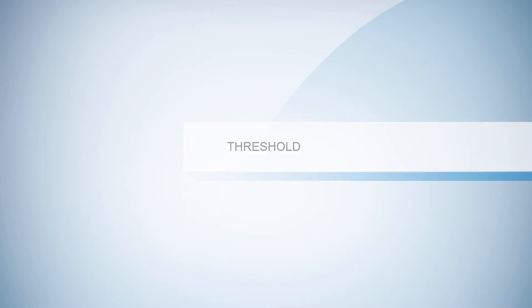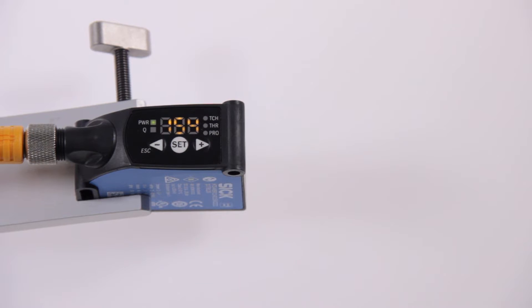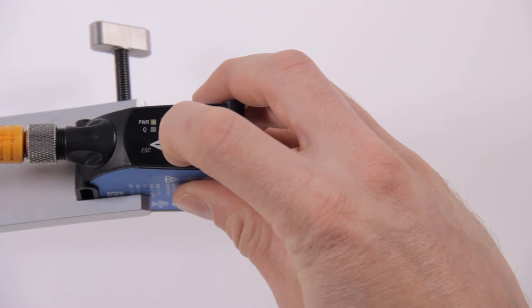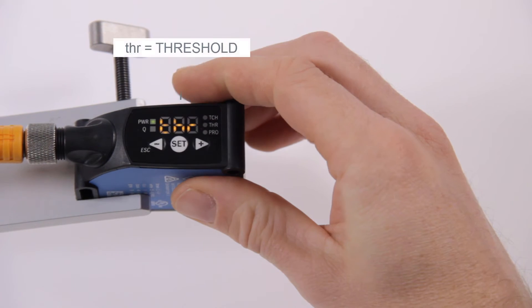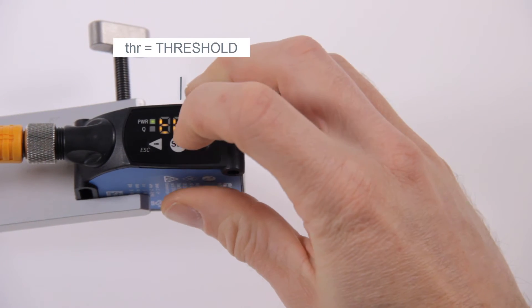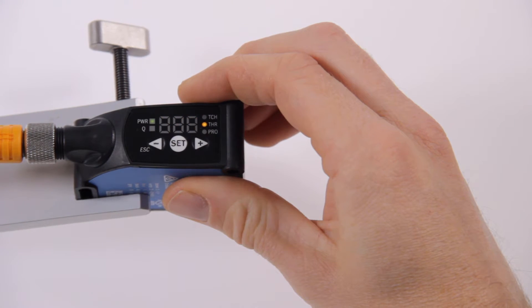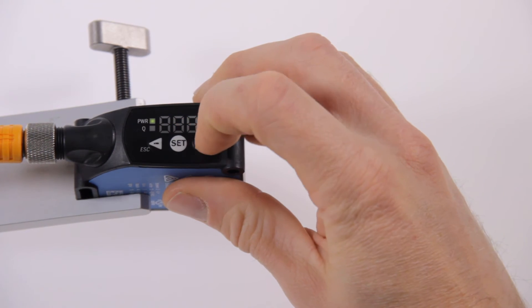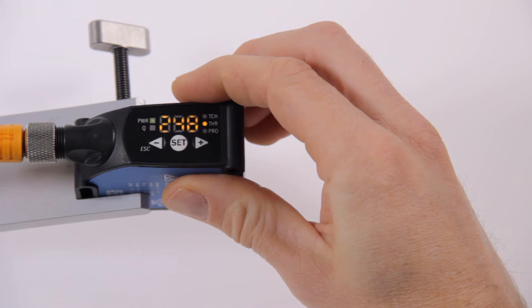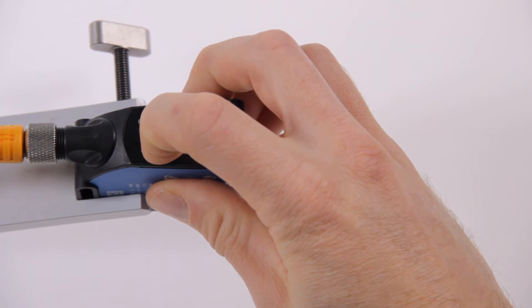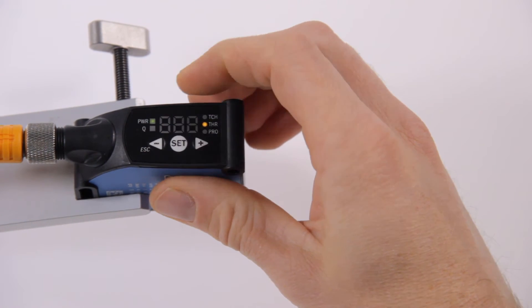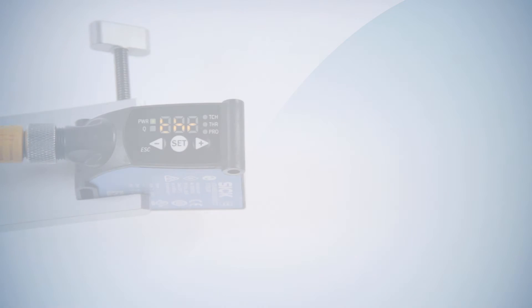Threshold. The automatically set threshold can be adjusted manually as well. Use the plus and minus buttons in order to navigate to THR for threshold. Confirm with SET. The shown remission value is the value that was set during teach-in, exactly in between the value of the mark and the background. Use the plus and minus buttons to move the threshold closer to the mark or the background. Confirm the new value with SET.